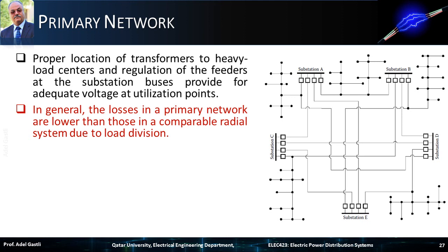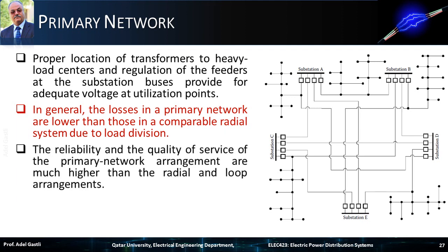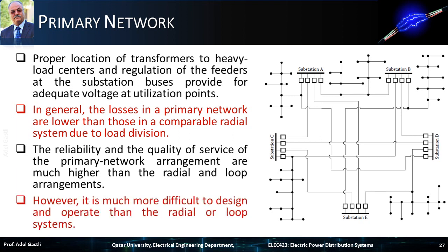In general, the losses in a primary network are lower than those in a comparable radial system due to load division. Besides, the reliability and the quality of service of the primary network arrangement are much higher than the radial and loop arrangements. However, it is much more difficult to design and operate than the radial or loop systems.